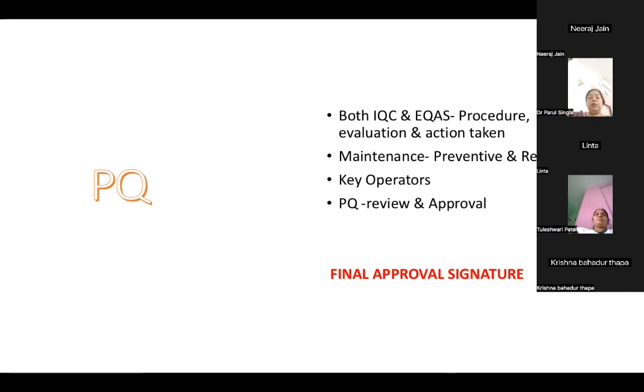Who will be the key operators? One or two of them should be trained on handling day-to-day troubleshooting, which can be solved after talking to the engineer. Then make a PQ report in which you have done a BRI verification. If you have done a precision study, if you have done an accuracy study, what is your protocol for low volume tests? What is your protocol for high volume tests, if any, or is the protocol the same for any analyte in the lab, irrespective of the sample load?